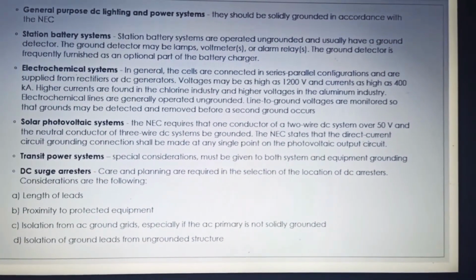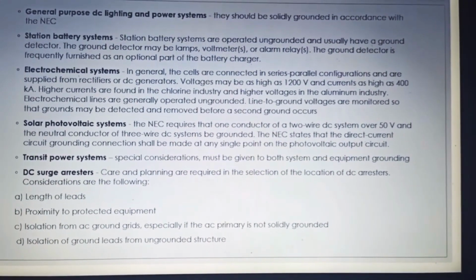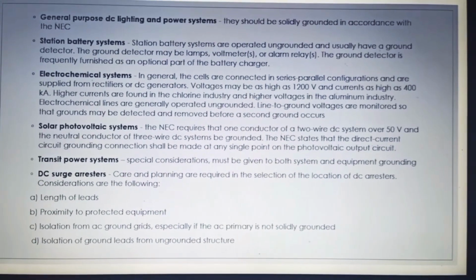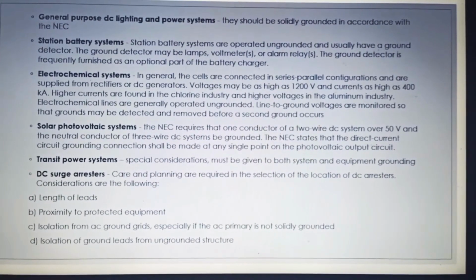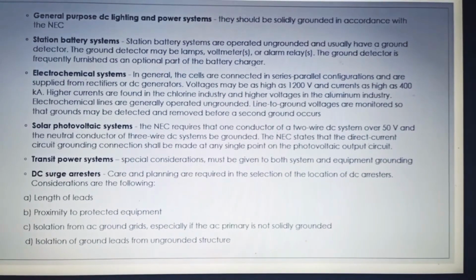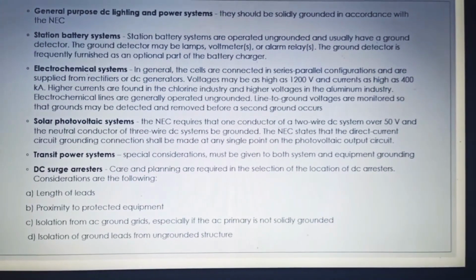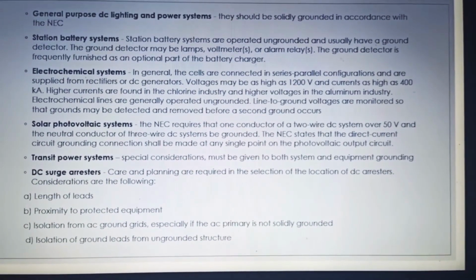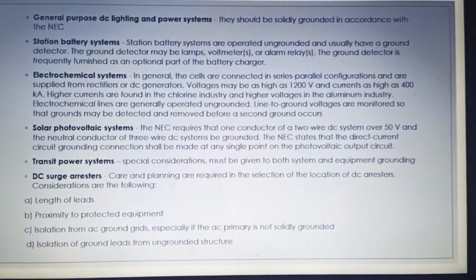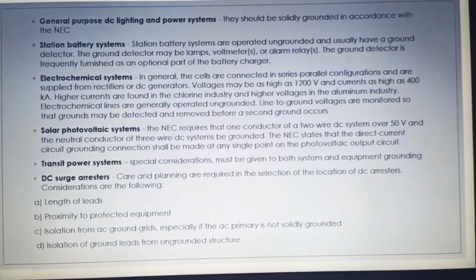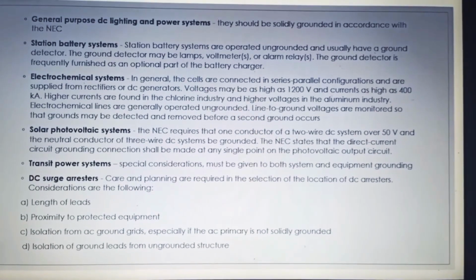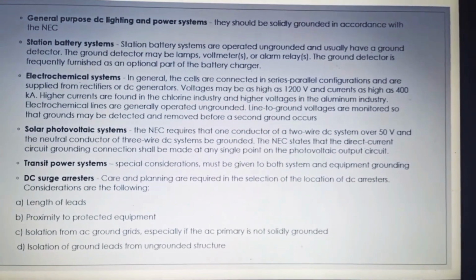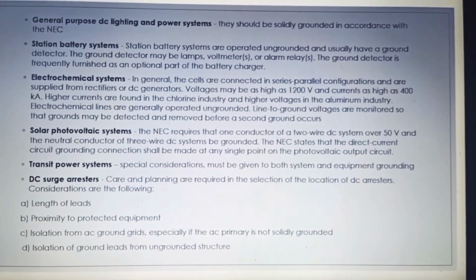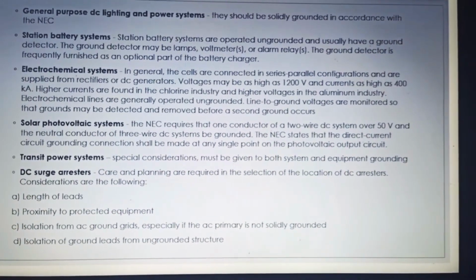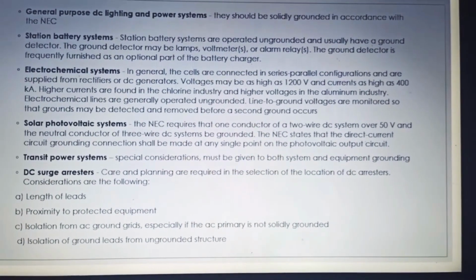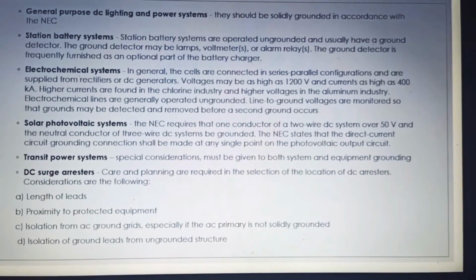Photovoltaic systems. The NEC addresses the grounding of solar photovoltaic systems. For a photovoltaic power source, the NEC requires that one conductor of a two-wire DC system over 50 volts and the neutral conductor of a three-wire DC system be grounded. An exception states that other methods that accomplish equivalent system protection and that utilize equipment listed and identified for the use shall be permitted.